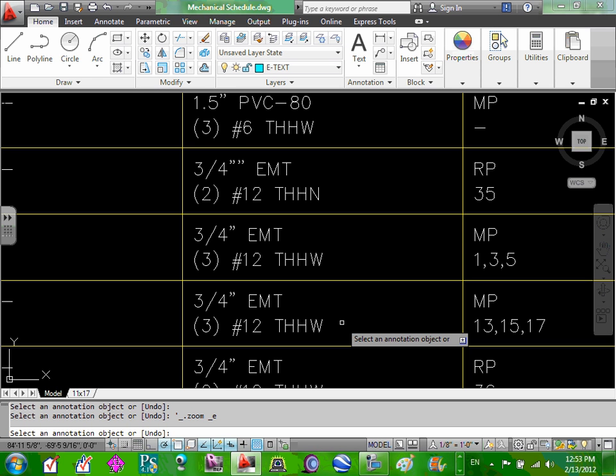So remember it was 7.5. You multiply 7.5 times 1.25, you're going to get 9.4 amps. I can pick this one with number 14 conductor, guys. But you don't want to use anything in commercial less than number 12. So you have 3 conductors, number 12.